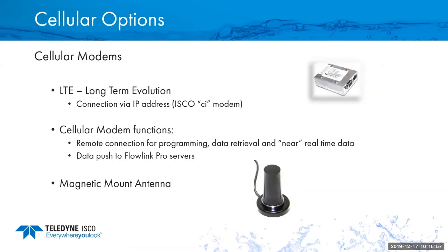Cellular modems are another way to get you connected to the signature meter remotely. So you could use the LTE CI version, or if you're in a location with GSM, so either the CI is Verizon, or GSM would be AT&T, T-Mobile, or some other GSM provider. What you can do then is connect to the device via static IP, download your data, look at the screens, things like that, make changes to programming remotely, or use the cellular modem to push the data into a FlowLink Pro server as well and get your alarm conditions sent out via email or text.